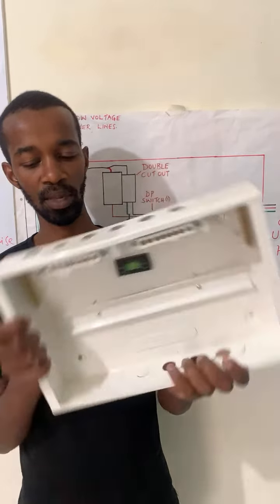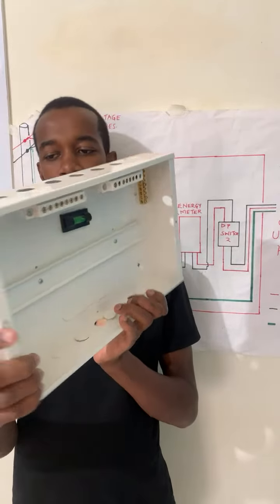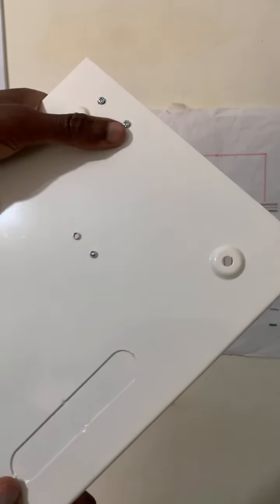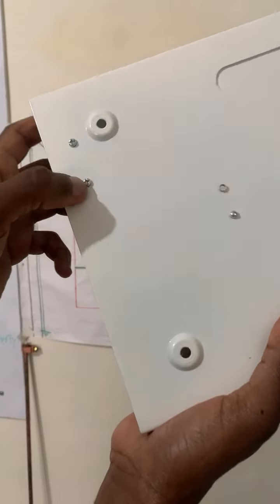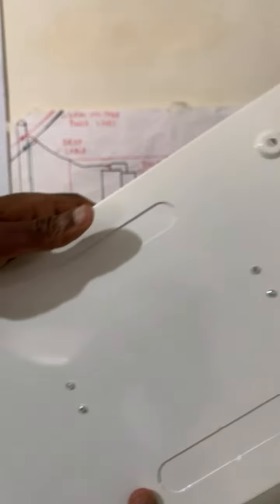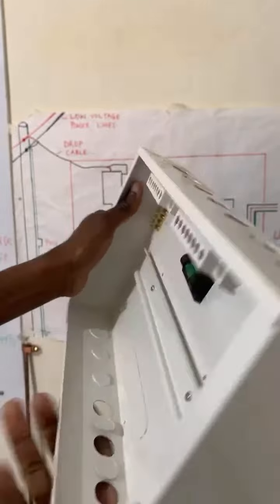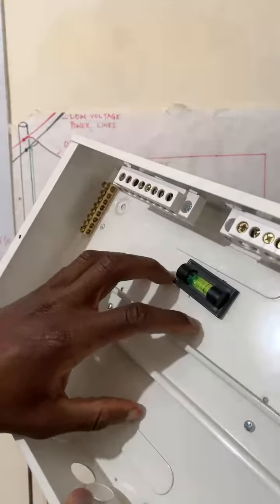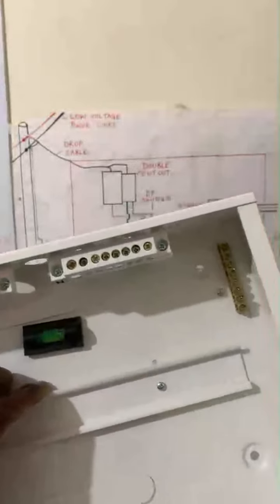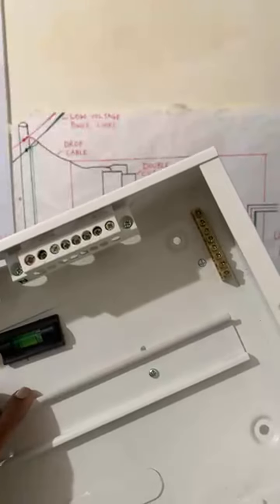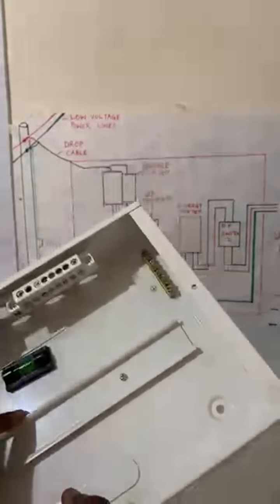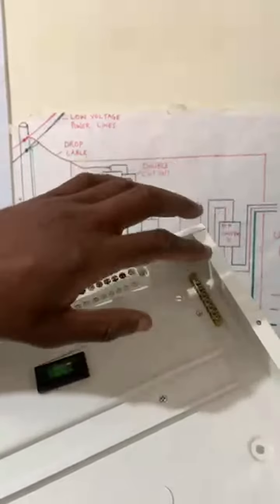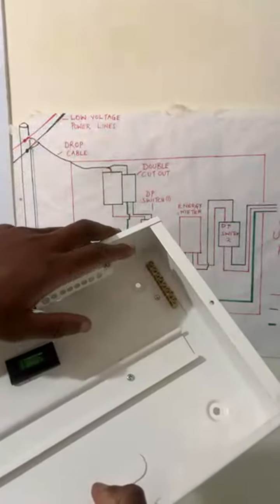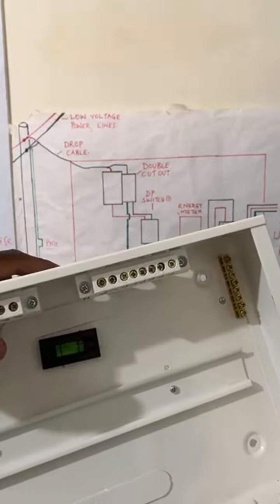Now, let me touch on something. You see these two earth bars that are here are in direct contact with this metallic consumer unit. How? If you can see at this back point here, look at that. It is directly connected, as you can see. So that means that these earth bars are in contact with the consumer unit, which makes the entire consumer unit earthed as well. Remember, we talked about earthing each and every electrical part that is metallic. So that is how the consumer unit also finds itself being earthed, by the fact that it is metallic. That is something so interesting about the design of the consumer unit.